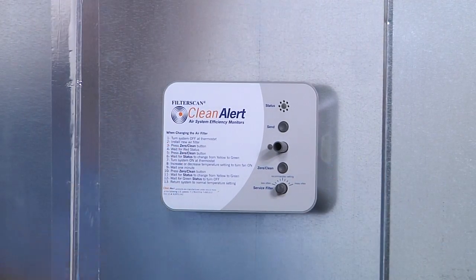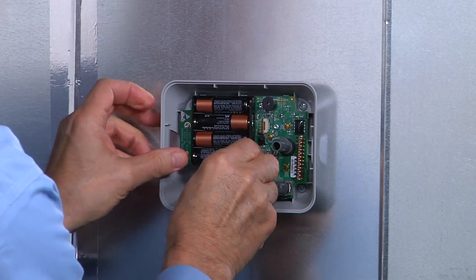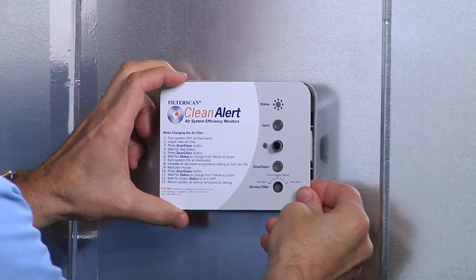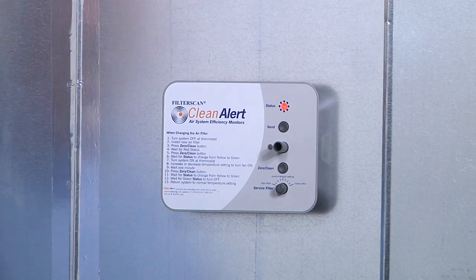The conduit-powered models should be installed by a qualified electrician and are powered from the HVAC system's auxiliary 24-volt AC or DC power supply. A typical installation will have that power run through installer-provided conduit to the Filterscan monitor. After power is turned on, the status LED should come on green momentarily, then turn on and remain red. This indicates that the unit has not yet been calibrated to the air filter and HVAC system upon which it is installed. Wait approximately 15 seconds for warm-up and stabilization.